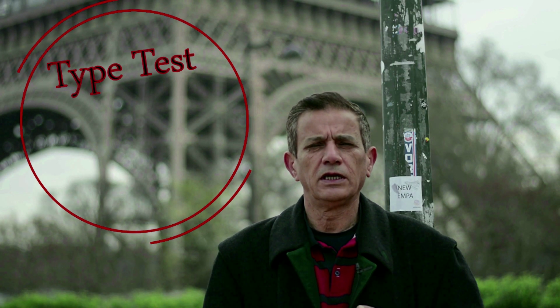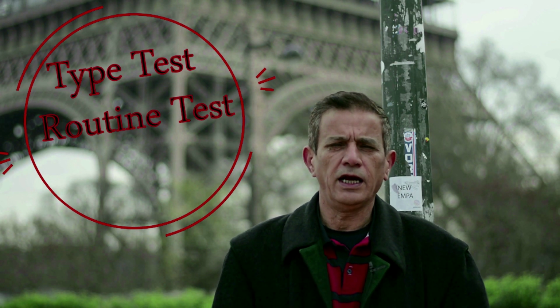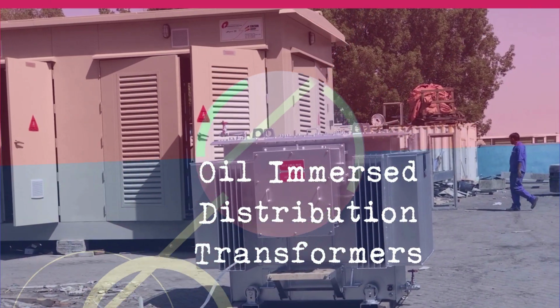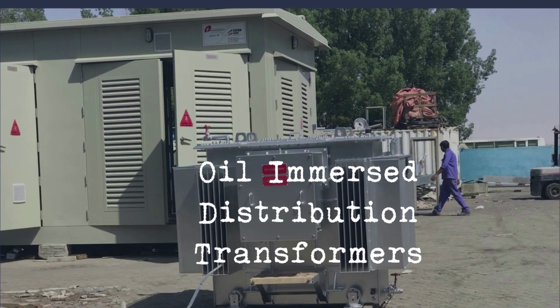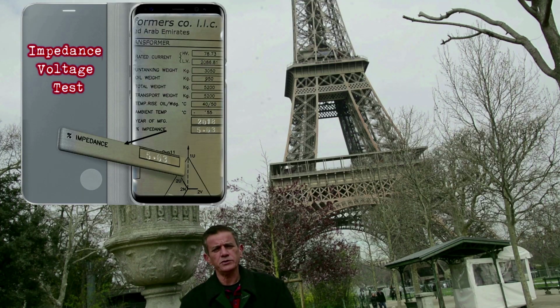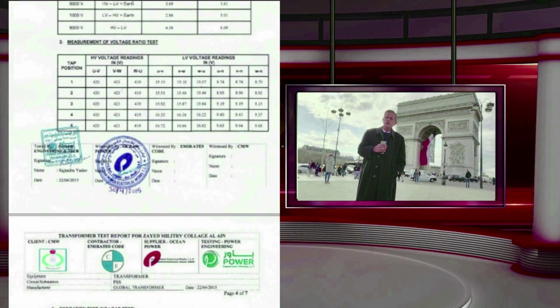Type test, routine test, and special tests. Impedance voltage test, or the percentage impedance. The results taken from the factory or from the site.